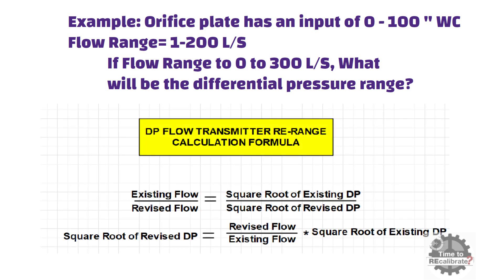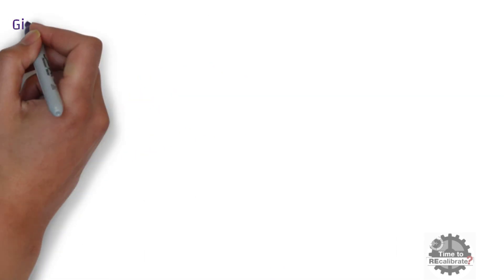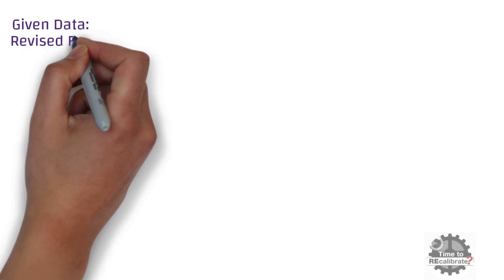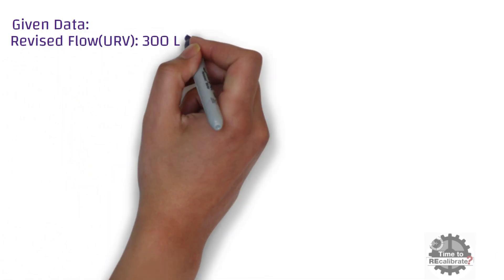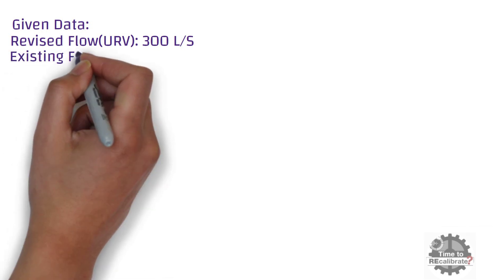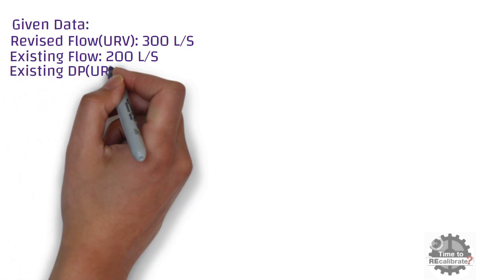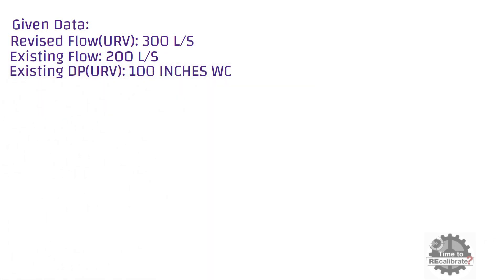As you can see, this is a standard calculation formula to calculate differential pressure range. Let's write down the data given in this example. The revised flow upper range value is 300 liters per second, the existing flow upper range value is 200 liters per second, and the existing differential pressure upper range value is 100 inches of water column.